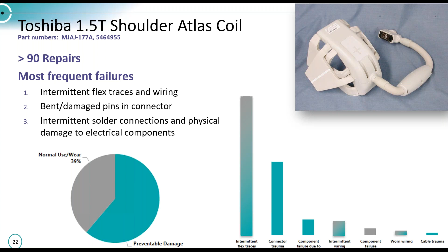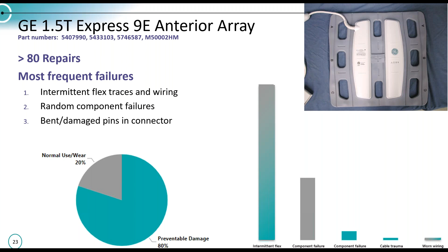Another type of flex coil, a larger type of flex design, is the 1.5T Express anterior array. So this would be laying on top of the patient as they're laying on the table inside the magnet. Again, with flex coils, we see a lot of intermittent traces. It could be in the flex coil themselves or the trace circuitry themselves that just wear out from continual flexing. But again, with that comes people carrying, the users carrying these around like suitcases by those, I hate to call them handles, they're not handles, but they sure as heck look like handles on there, where you see the A, B, and C on the coil photograph there. But anytime a coil is transported using one of the flexible sections of the coil, you're inducing stress to the underlying components and flex circuitry that's underneath that flexible foam.